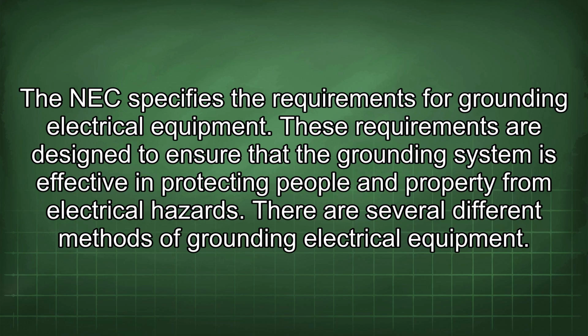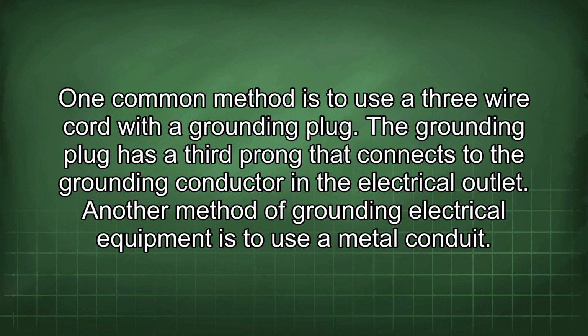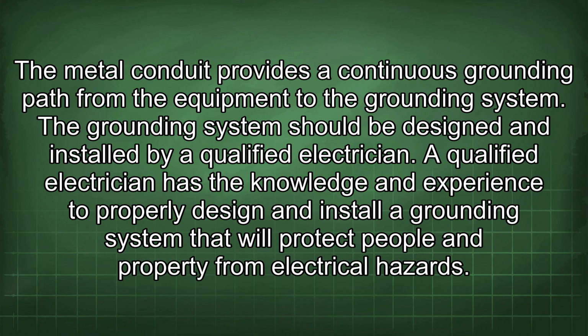There are several different methods of grounding electrical equipment. One common method is to use a 3-wire cord with a grounding plug. The grounding plug has a third prong that connects to the grounding conductor in the electrical outlet. Another method of grounding electrical equipment is to use a metal conduit. The metal conduit provides a continuous grounding path from the equipment to the grounding system. The grounding system should be designed and installed by a qualified electrician. A qualified electrician has the knowledge and experience to properly design and install a grounding system that will protect people and property from electrical hazards.